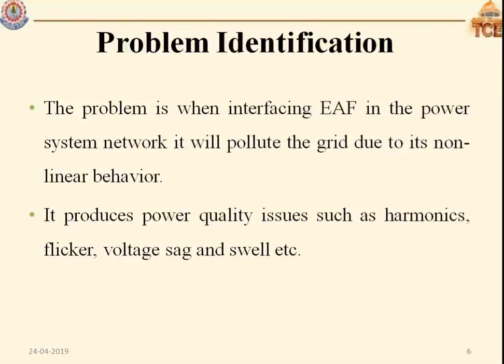To mitigate these power quality issues, we have to install some FACTS devices such as STATCOM, SVC, static power compensator, and passive filters and active filters, but it is very costly and not economical. And due to the load varying nature of the arc furnace, the predictability of harmonics is uncertain. It varies due to the loading of scrap metals in the furnace.